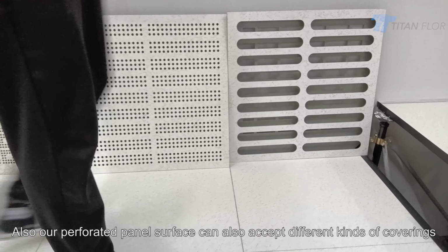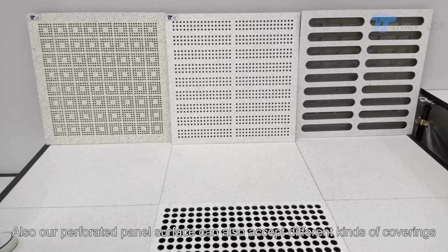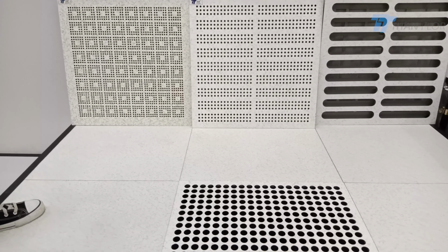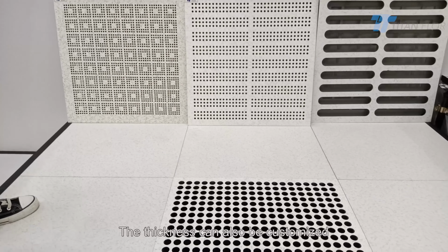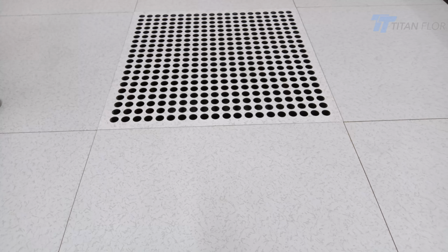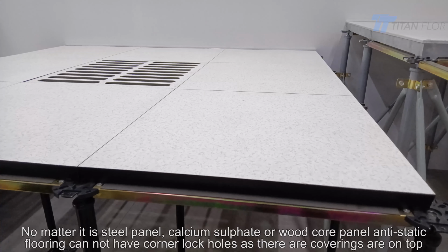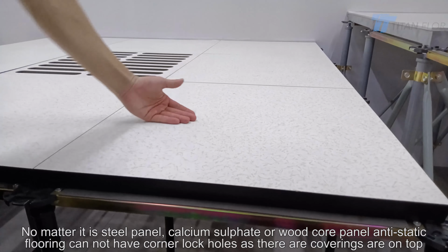Also, our perforated panel surface can accept different kinds of coverings, and the thickness can also be customized. They can be used together with all kinds of anti-static floorings, like steel flooring, like calcium sulphate flooring, like wood core flooring. No matter it is steel panel, calcium sulphate, or wood core panel, anti-static flooring cannot have corner lock holes, as there are coverings on top.